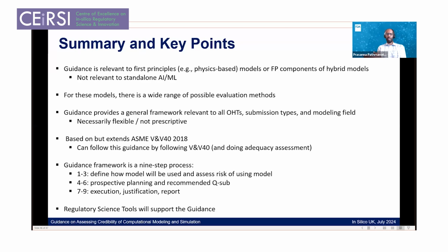And that's because of the constraints that we have with first principles based models and the lack of data generally. The guidance provides a general framework relevant to all OHTs of the different offices within the regulatory side of CDRH, the devices center. So basically all different types of medical device, all submission types, and all modeling fields, at least first principles. So that makes it necessarily flexible and not prescriptive.